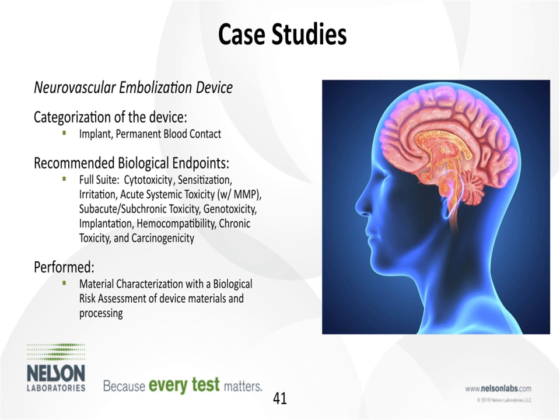I will be moving on now to our last slides, which are to cover case studies and to really look to see how material characterization or chemical characterization was used. The first case study that I'll be talking about is a neurovascular embolization device. This particular device is made up of nitinol, which is a nickel-titanium alloy. This alloy is literally placed inside the aneurysm sac across the neck of the aneurysm to deflect blood and hopefully prevent that aneurysm from rupturing.